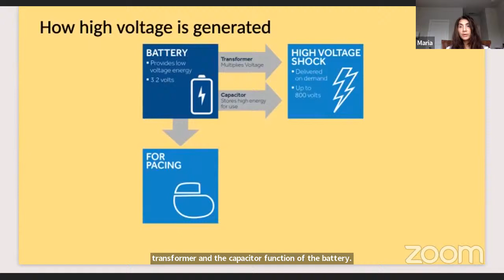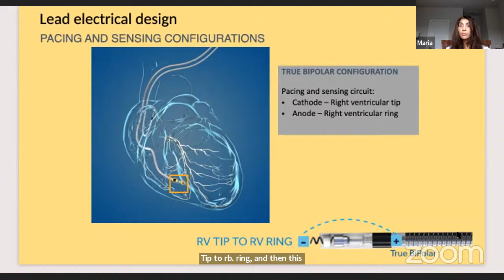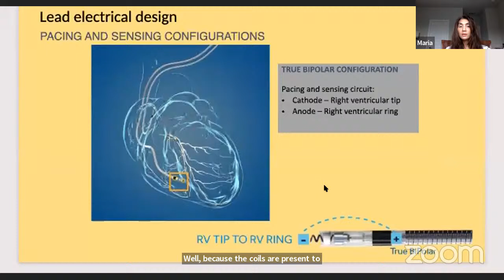The shock is really painful, but it's life-saving. The leads are a little different from pacemaker leads. If you look at the tip, this is a bipolar RV tip to RV ring, and then this is the shock coil, because coils are present to deliver the high voltage impulse to the ventricular myocardium to defibrillate the heart.